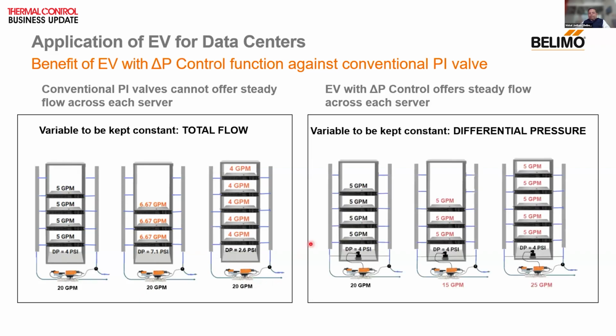With the current setup, by adding these delta P sensors in the energy wall, we can modulate the flow coming from the CDU, whereas the flow across the rack and the pressure difference across the rack remain the same. So in all permutation combinations, the flow and the pressure difference across the rack remain the same. That's the unique feature that we have to offer for liquid cooling.